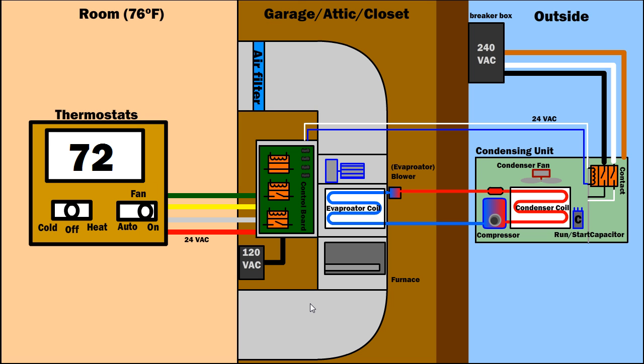And if you made sure that there's airflow and the fan turns, then you can move on to the next test. Turn the fan back to auto and now let's push it over to cool. If you set the thermostat to let's say 72 degrees lower than what the room temperature is, then the very first thing like I said before, 24 volts goes through this control board into thermostat and back out to the control board and closes the relay. This kicks on the evaporator blower.